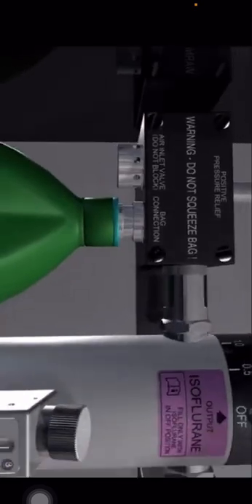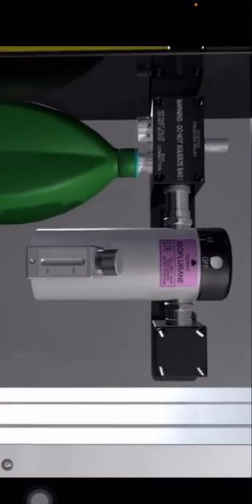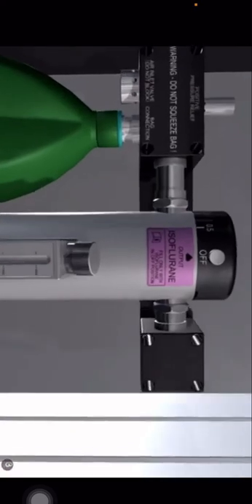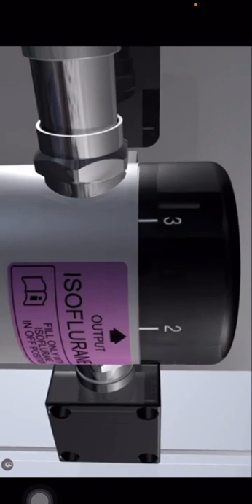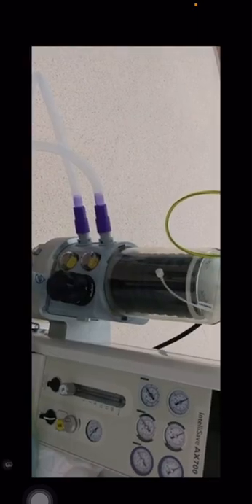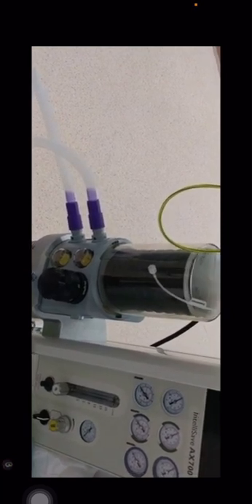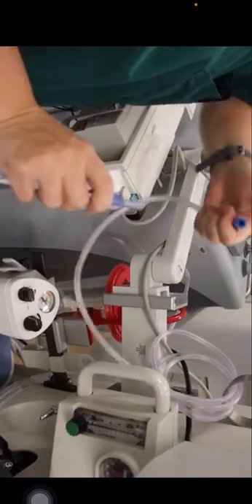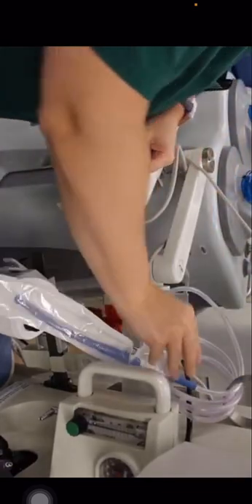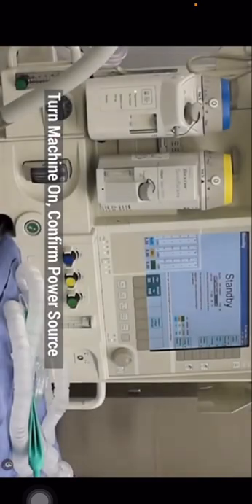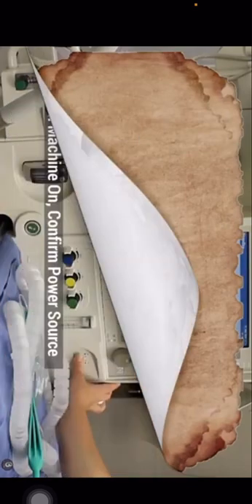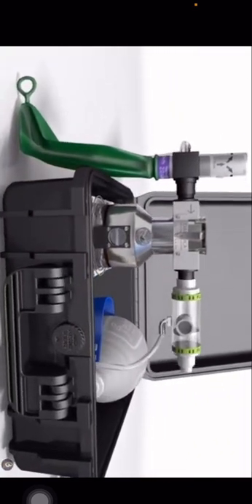The system for monitoring the patient's heart rate, ECG, blood pressure, and oxygen saturation may be incorporated, along with monitoring of end-tidal carbon dioxide and temperature. Breathing systems are also typical components, including a manual reservoir bag for ventilation combined with an adjustable pressure limiting valve, as well as an integrated mechanical ventilator.